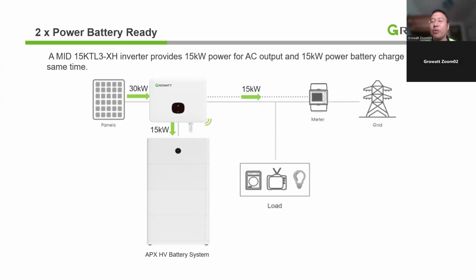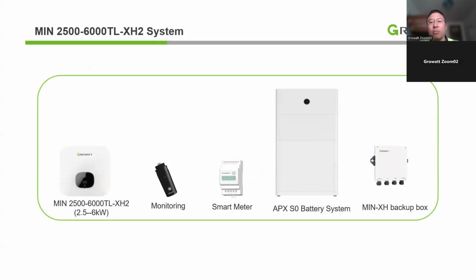So our inverters, say a 15 kilowatt inverter, can charge the battery at 15 kilowatt and feed back to the grid at 15 kilowatt simultaneously. That means it can handle at least 30 kilowatt of solar panels, or 200% DC oversizing. All right, this is some of the material list, more for when you do the quotation.